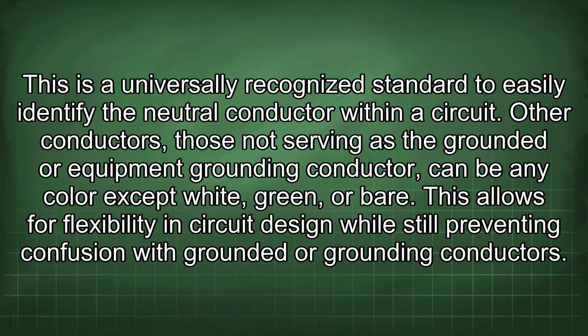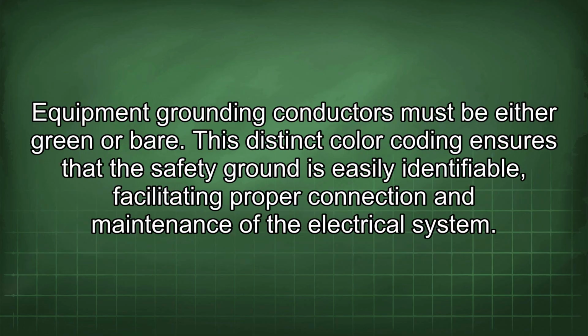Other conductors, those not serving as the grounded or equipment grounding conductor, can be any color except white, green, or bare. This allows for flexibility in circuit design while still preventing confusion with grounded or grounding conductors. Equipment grounding conductors must be either green or bare.